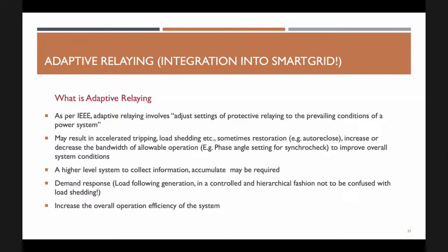On the low voltage system, again, the simple overcurrent time grading may not work anymore. We have power flowing here and there and everywhere, and we need to make sure cables don't get overloaded, in addition to making sure protection works, because earlier the loading was done in such a way that cables didn't get overloaded and we weren't bothered about it so much. But tomorrow we need to make sure we have the right settings, and we need to look at different scenarios - faults happening in different places depending on weather conditions, whether solar energy is going to be in place, what the fault current is. So fault studies and other things are going to be much more complicated.